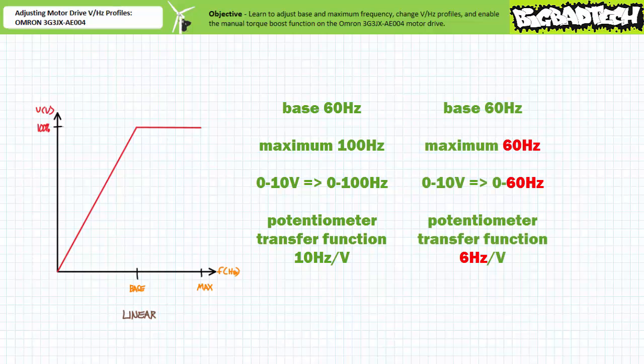If one reduced maximum frequency also to 60 hertz, this doesn't really change the performance all that much besides limiting maximum speed. As previously, from zero to base frequency, applied voltage would be linearly proportional. Given base frequency happens to be maximum frequency, applied voltage would cease to increase as would frequency. Really the only difference is that the external speed potentiometer's zero to 10 volt analog voltage input would now be automatically scaled to represent only the zero to 60 hertz range.